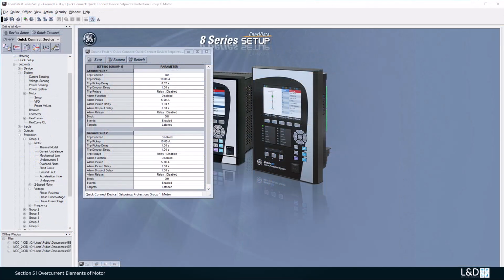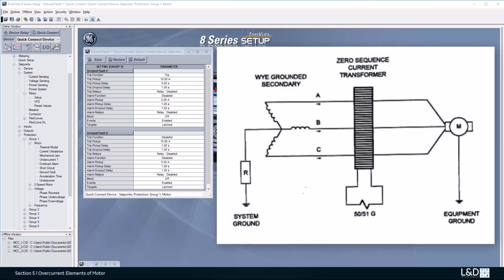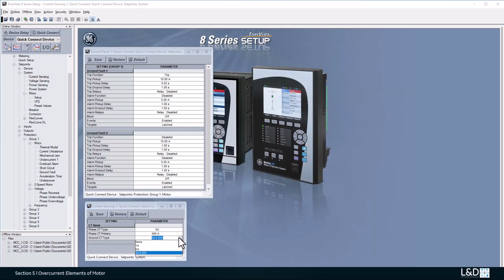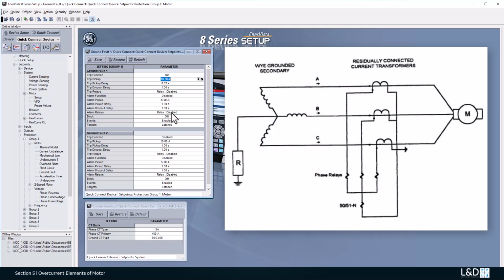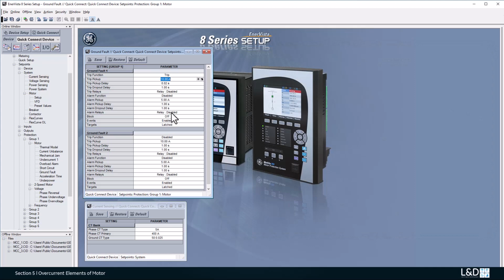The ground fault input can be from a zero sequence CT or core balance CT, which provides higher accuracy. When the ground CT type is set to 50:0.025, then the pickup range is from 0.25 to 25 amps. Another way is to use the residual connection, if the cables are too large to fit through the zero sequence CT window or the trench is too narrow to fit the zero sequence CT. This configuration is inherently less sensitive than that of the zero sequence configuration.